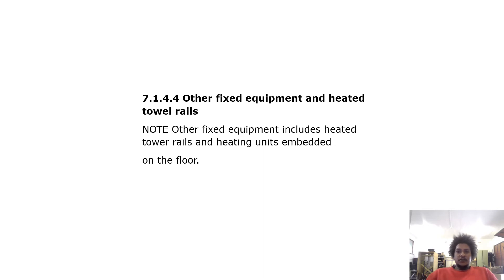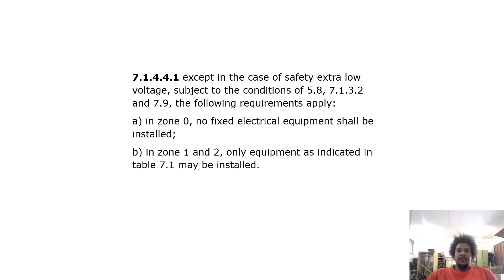Other fixed equipment and heated towel rails: note that other fixed equipment includes heated towel rails and heating units embedded in the floor. Except in the case of SELV, subject to the conditions of 5.8, 7.1.3.2 and 7.9, the following requirements apply: in zone 0, no fixed electrical equipment shall be installed; in zones 1 and 2, only equipment as indicated in Table 7.1 may be installed.